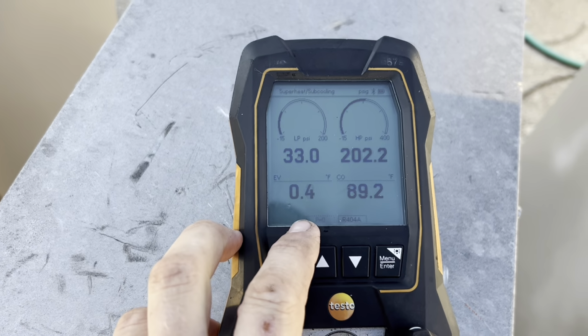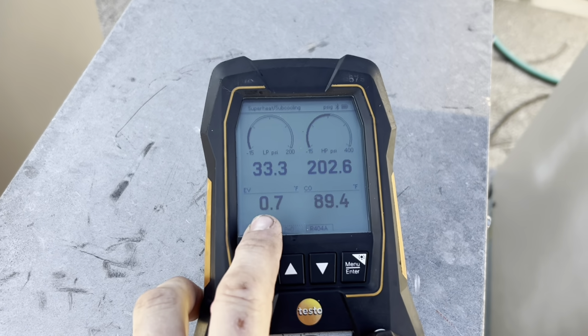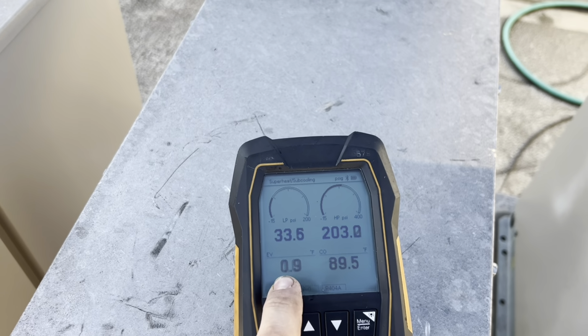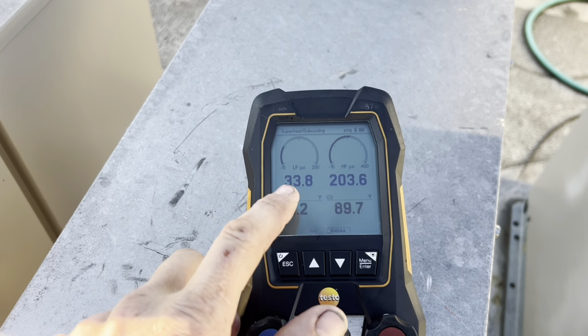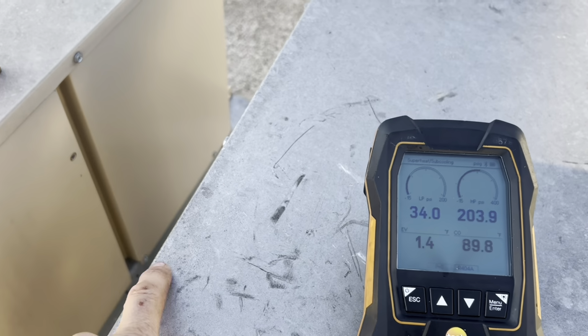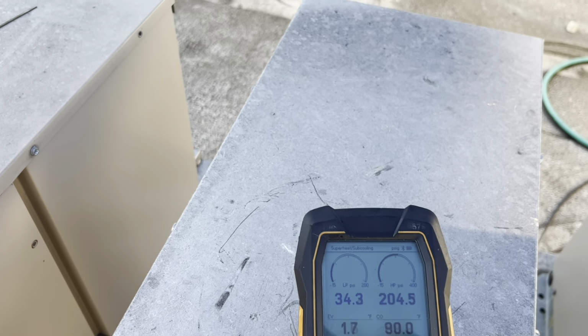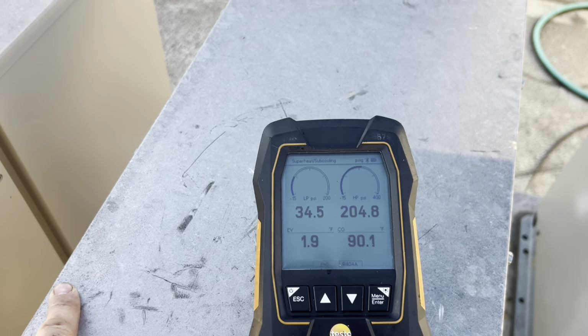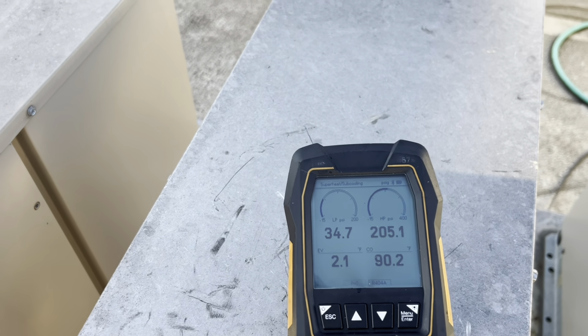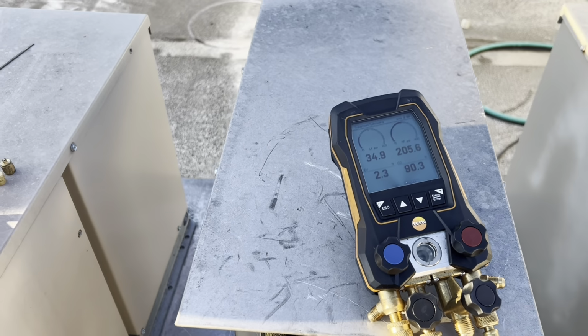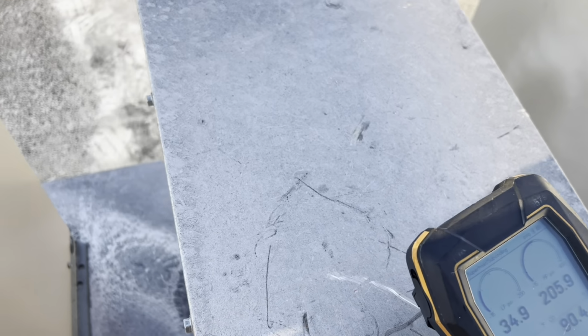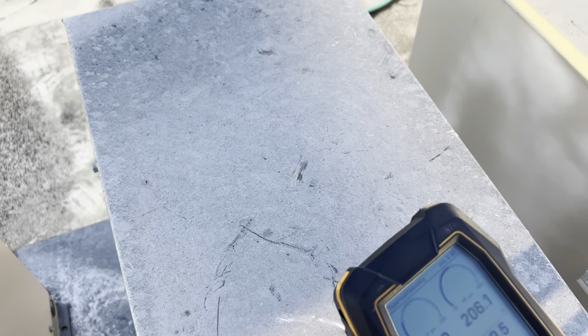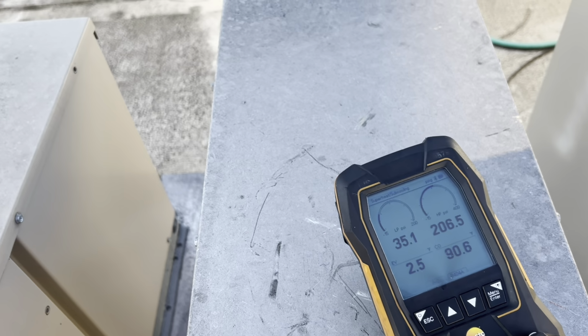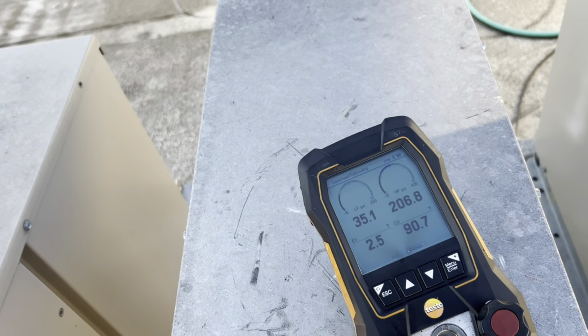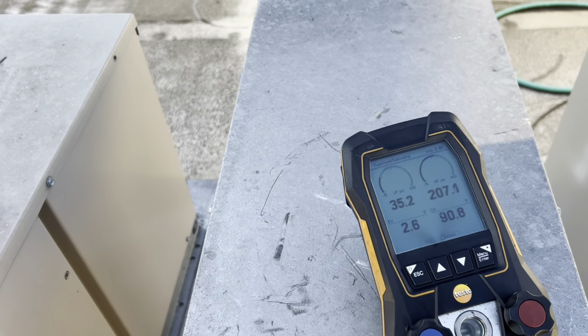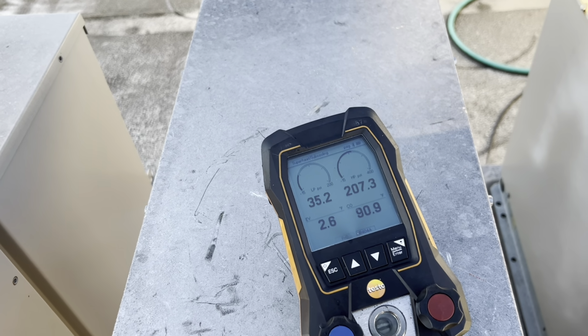Which would be good to go down and check to see what it says. We can do that through the screen, I'll show you. A suction pressure transducer tells you the pressure inside the evaporator, and it also has a temperature probe, and it uses that to dial in superheat. So why would it have been short cycling? Trying to dial in superheat, it's definitely not going to mess with the solenoids, but having bad temperature probes is definitely a thing.